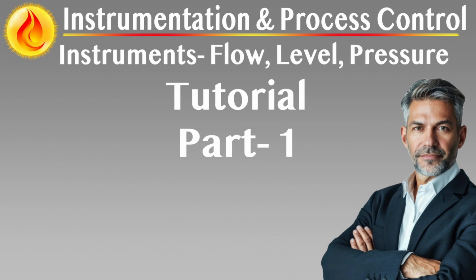Power supply design must reflect application criticality. Instruments serving safety, trip, or essential control functions must be powered from uninterruptible sources, 24-volt DC or 115-230 VAC, with operational stability guaranteed through full immunity to voltage dips, brownouts, or UPS switchover transients. All components must be verified to tolerate such events without signal loss or reset behavior.